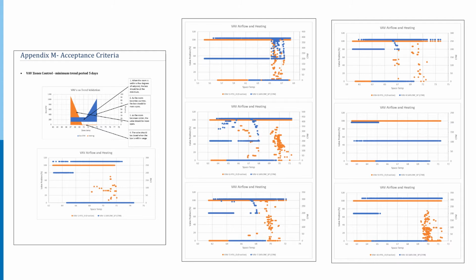Kind of the same thing on the blue side. You should never really see blue dots up at the far left side of the graph, right? That represents a zone that's cold, and it's using 100% of the air in the zone, which really shouldn't happen. So here we're seeing those blue dots kind of all over the place. And this is every zone. I didn't show every zone here, but these pictures look pretty similar across all the zones.